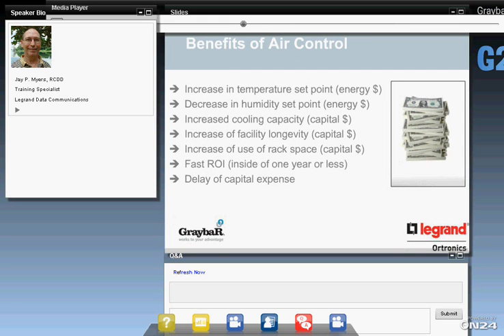So these are the benefits. If we can control the air better, we can keep the cold air where we want it and the hot air where we want it. We can edge up the temperature set points and edge down the humidity set points. Most recommendations now are for 30% rather than 50%. We cool better, protect your equipment, and increase the longevity. If we can fill up the racks better, then you use that space more efficiently, and that next 25,000 square feet of build out, we can put that off for 2 or 3 years. That's a huge savings. And most of these are fairly simple devices and easily installed. So the return on investment for most of everything you're going to see here is less than a year. There's not very many things you can put in a data center that pay for themselves in a year.